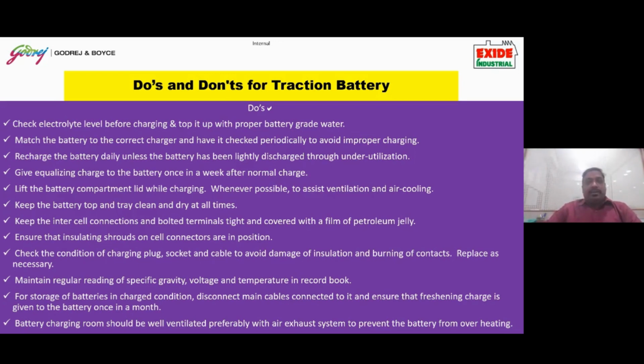Before charging, the lid must be opened and the electrolyte level must be checked. If there is some deficiency in the electrolyte, remember, no sulfuric acid, but only battery grade DM water should be added and topped up, and then the battery should be put on charging. If you add electrolyte after charging, then the concept of electrolyte stratification will come into force, and you might not get appropriate capacity from that cell.